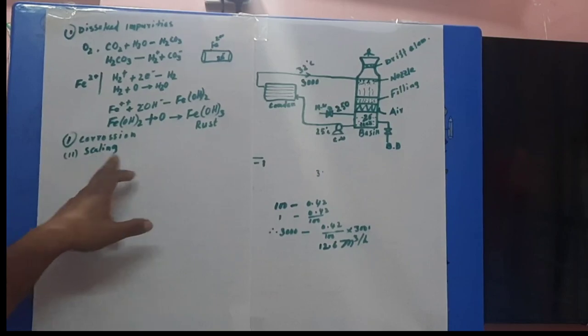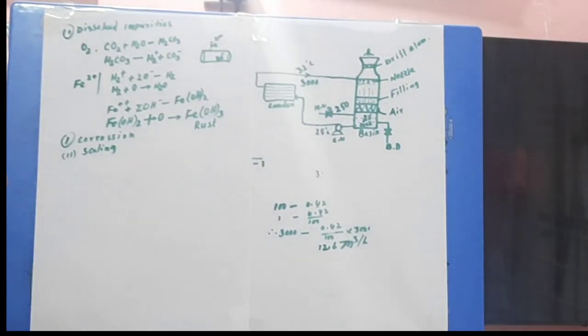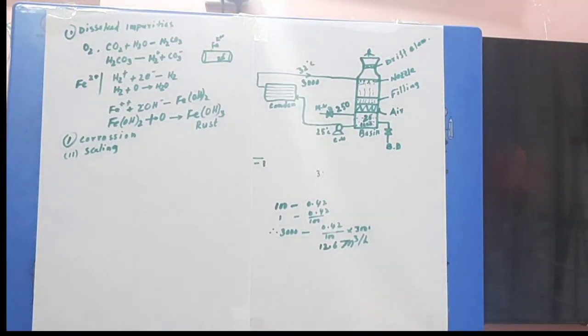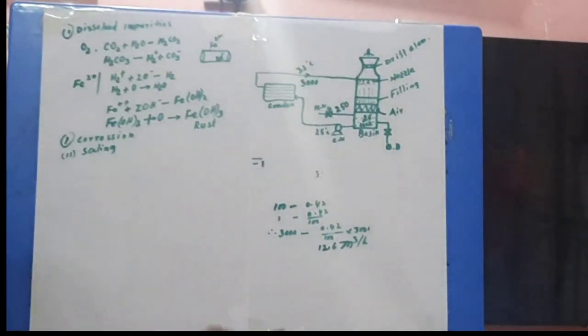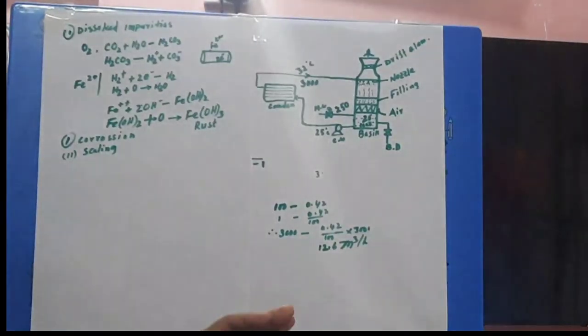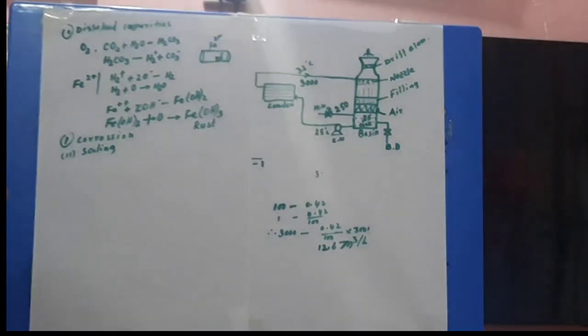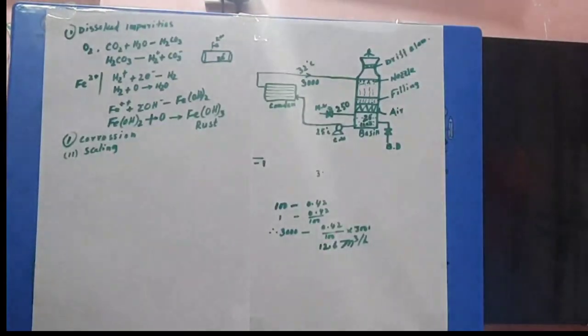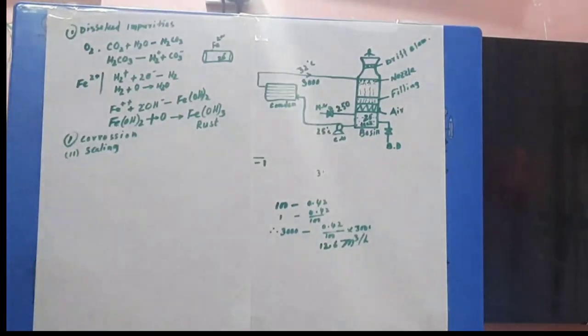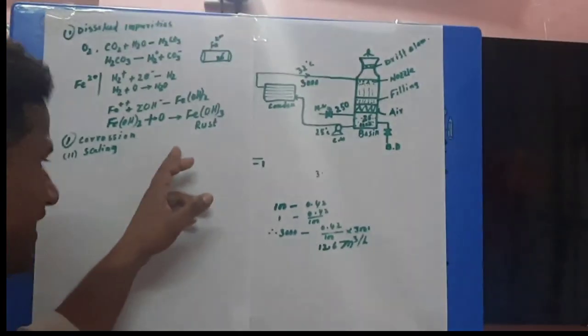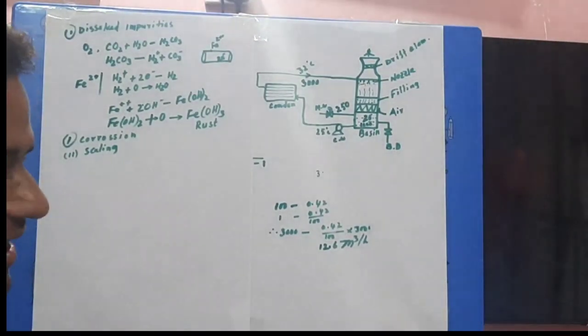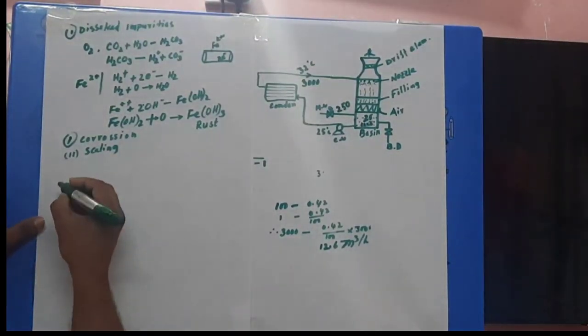Scaling happens when dissolved impurities like calcium carbonate, magnesium sulfate, and sodium sulfate are present in the cooling water. These salts go to the condenser and deposit on the condenser tube, blocking it. To control scaling, you have to provide a scale inhibitor.